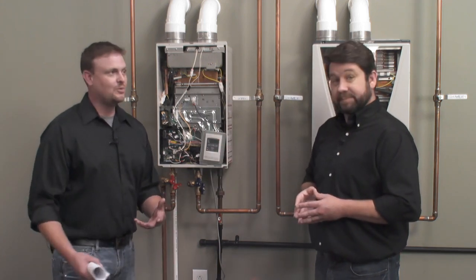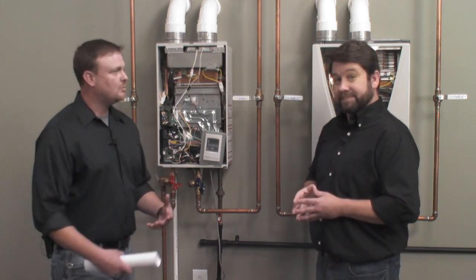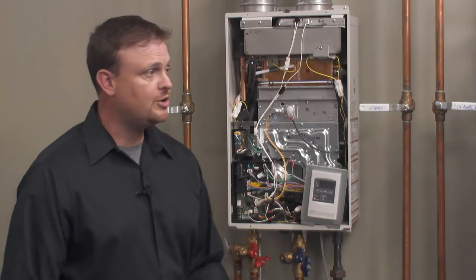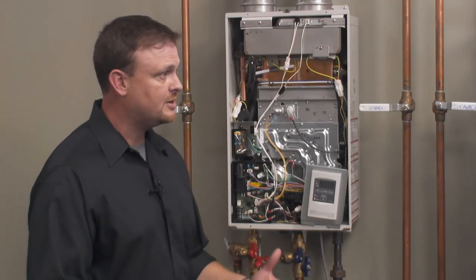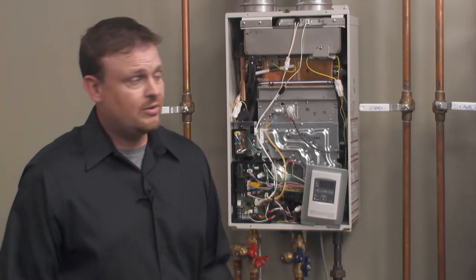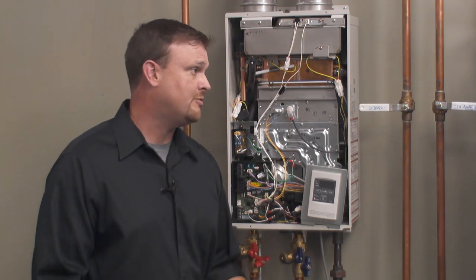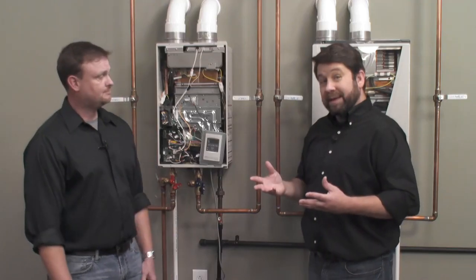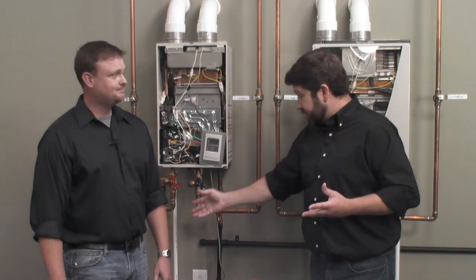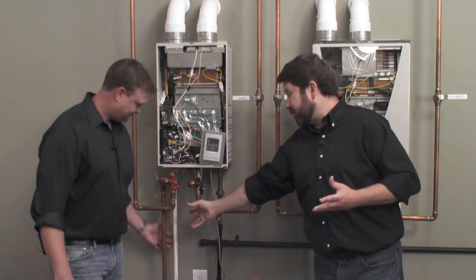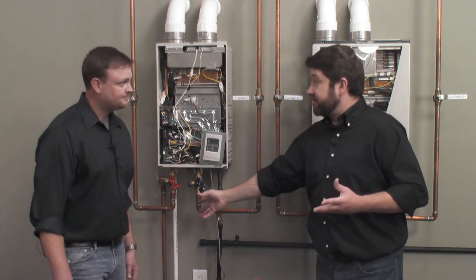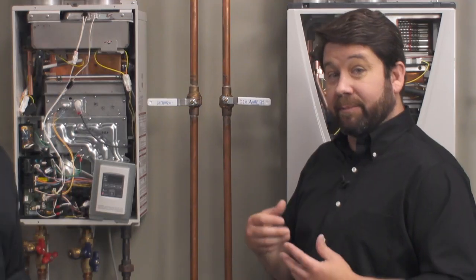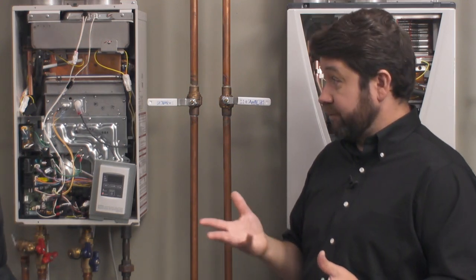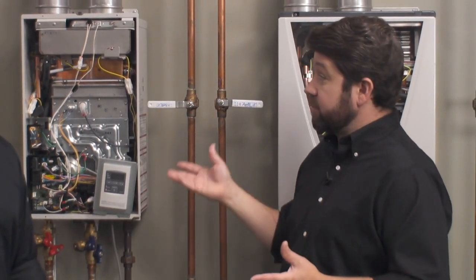Yeah, that's where you really want to, because if you stick it in a laundry room or something like that and you're using room air, you run the risk of lint and dust. And you do that with any atmospheric water heater that's not direct vented. One more thing is that it is condensing. So you see we've got an extra pipe coming down off of the bottom, and it's in PVC. So we are condensing. It's a byproduct of combustion, flue gases. Right. So it is acidic. So we need to dispose of that in a safe manner. We don't want to take it into a metal drain.